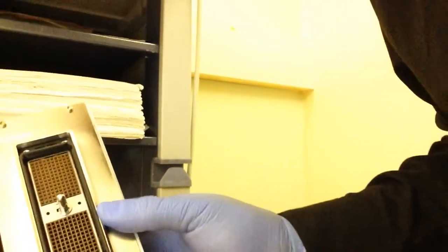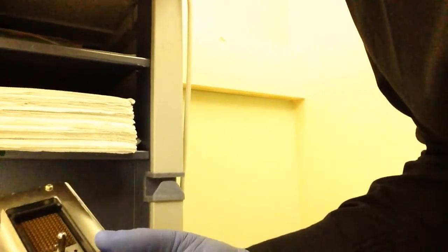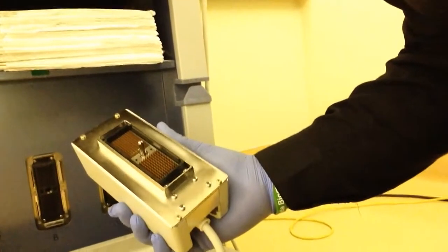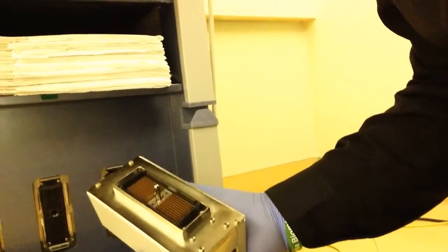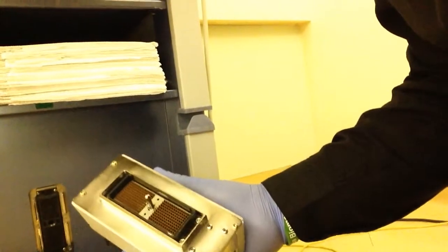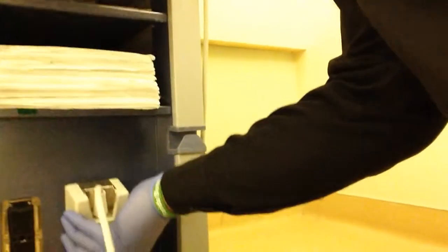Okay. So if they're LGA, you want to make sure that they're not dirty, that they're getting a complete connection. If they're pin grid array, PGA, you want to make sure that none of the pins are bent. Basically, if some of the pins are bent, you're not getting the full connection, meaning you're not getting the full voltage across the transducer. And when that happens, you won't get the right amount of frequency being produced across a piezoelectric material, so you won't get a very clear image. Also, the data being returned might not all be collected because some of the pins are damaged. So you want to go ahead and check that.